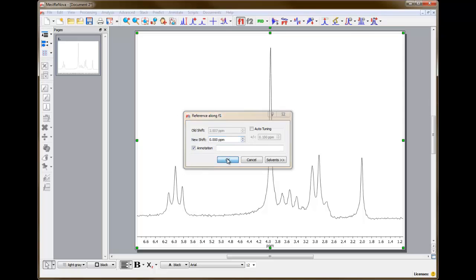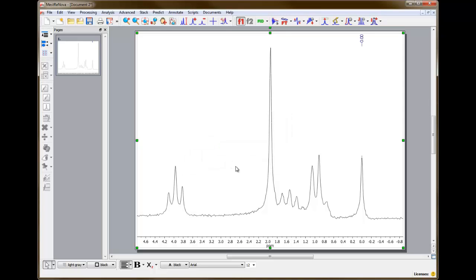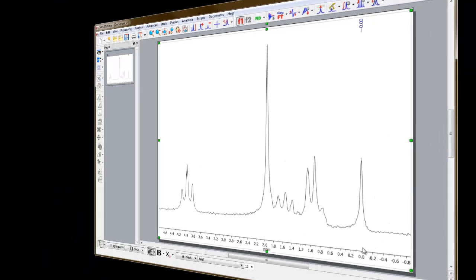If I didn't have TMS in my sample or used a different compound as a shift reference, I would then just select and assign a different signal in my spectrum as the reference peak. In most cases, we already have a good idea of the chemical shift of signals because the spectrum is known. If that's the case, then adding TMS is not required.